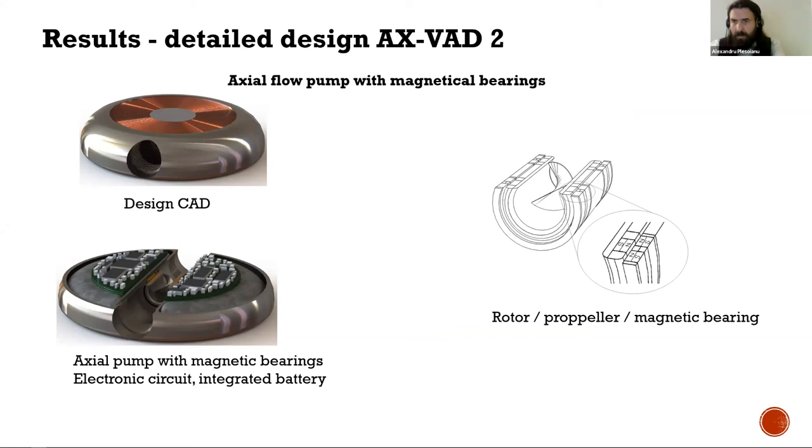The rotor is a two-layer tube, the inner one with a structural and shielding role, and the outer one with a rotational and bearing role. The tubular shape of the rotor allows the construction of the pump inside of it. The magnetic bearings consist of two components, the inner component attached to the exterior of the rotor and the outer component attached to the housing.